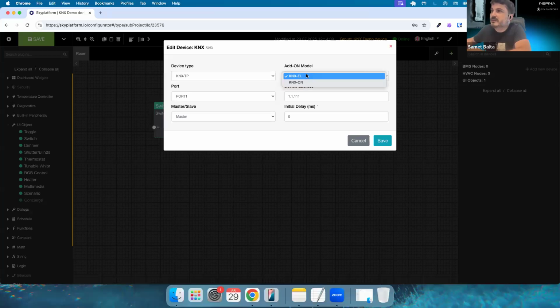For add-on type, KNX EL is used for previous models of KNX devices, and KNX ON is used for the latest generation KNX devices. I will choose KNX ON. And ports, for this device, we will have 2 physical ports. For example, you can insert your KNX add-on module on port 1, and you can choose port 2 for Modbus module, but we will go for port 1. A device address, communication address between Inspinia device and KNX device. Master and slave mode, or devices support both master and slave modes over KNX. It means in master mode, it periodically reads the status from the bus, while in slave mode, it only updates on device startup or when a command is received.